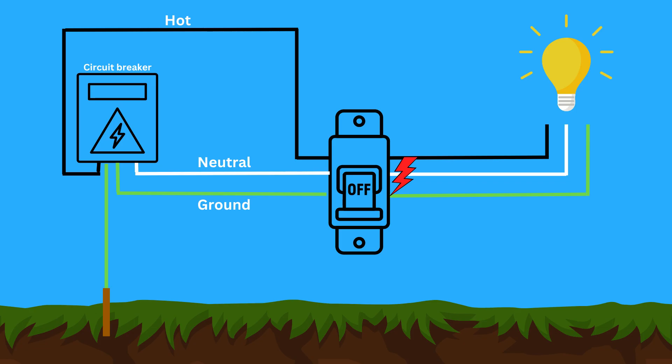Normally, electricity flows through the hot wire to your appliance and back through the neutral wire. However, if a hot wire comes into contact with a metal casing, the current will flow through the ground wire, resulting in a ground fault. This low resistance path causes a significant surge in current, tripping the breaker and cutting off the power to prevent harm.